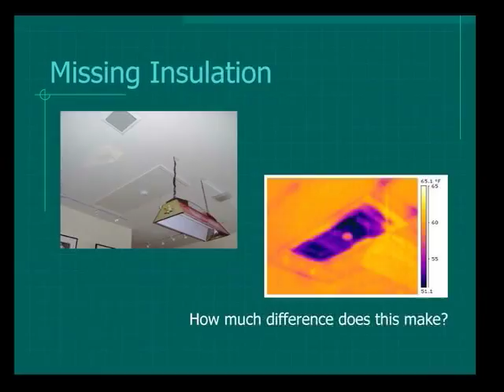So any guesses what that looks like from the energy perspective, looking at conduction losses from the house to the attic? Less than 1% of the square footage is in that spot, but remember the rest of the attic is insulated 38 times better than that one spot. If you work out the math, it comes out to about 20%. That one spot, 10 square feet, is worth 380 square feet from the energy perspective. So my whole attic effectively went from 1,500 square feet to 1,880 square feet — your attic basically just grew that size as far as energy is concerned.